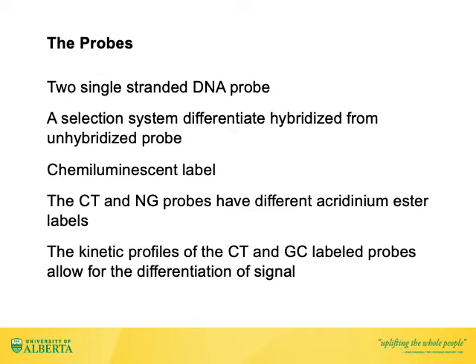As well as having two enzymes and three oligos, the chlamydia and gonorrhea assay uses two single-stranded DNA probes, one for each target. The probes bind the target RNA in between the capture oligo and the T7 oligo. Each probe is labeled with a different chemiluminescent ester and has a different kinetic profile, which allows differentiation of targets. There is a proprietary selection system that differentiates between bound and unbound probe.